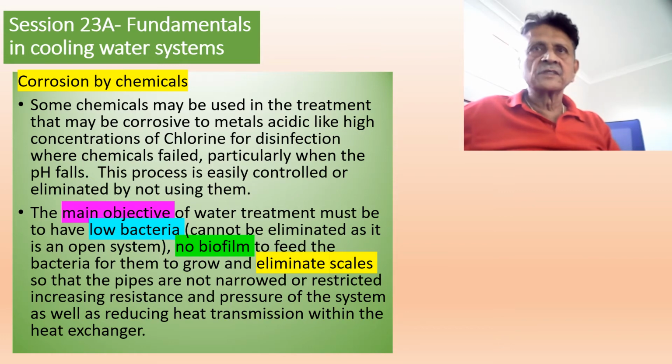Biofilm, of course, will activate the formation of scales, because when the water concentrates and becomes very saturated, crystallization of the calcium carbonate occurs, and the biofilm will act as a crystal around which the scales form.